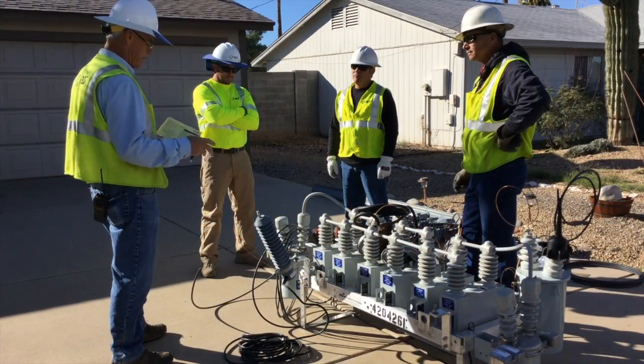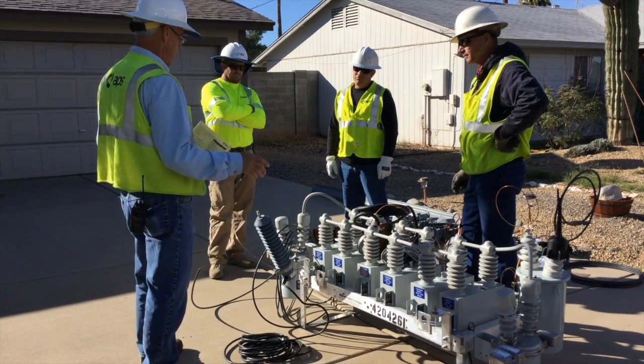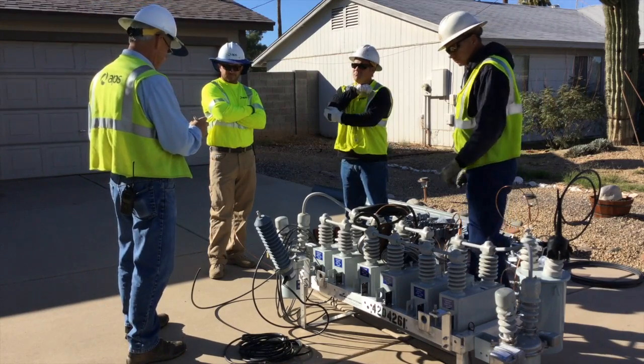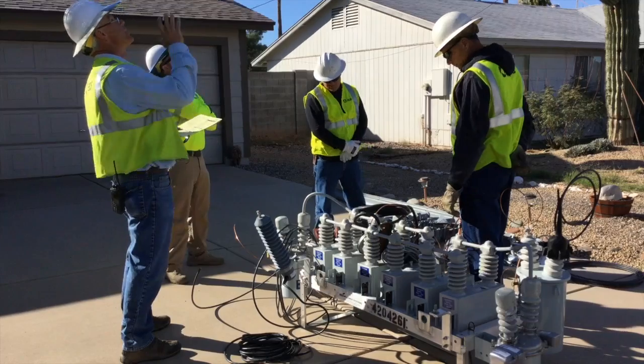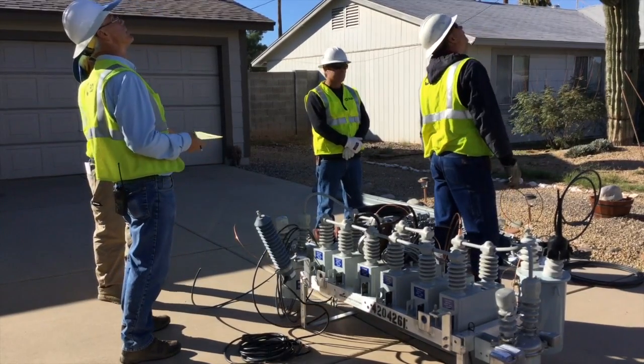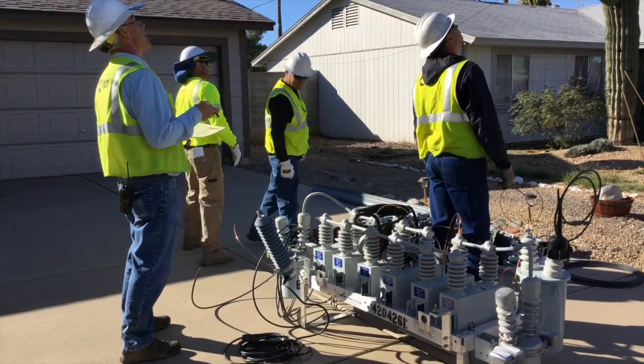Let's listen in to the pre-job briefing. We need to get our sensors put on and get it all ready to go. As far as the task assignment, Buck and Canning are going to be in the bucket doing the aerial work. We're going to install the new 1200 kVAR bank with smart grid upgrades, and we're also going to have to bring the pole up to spec with raptor protection.